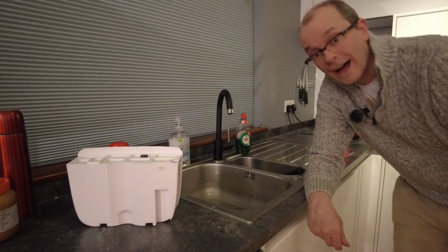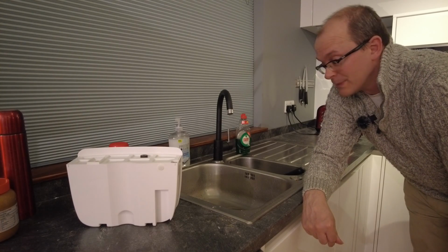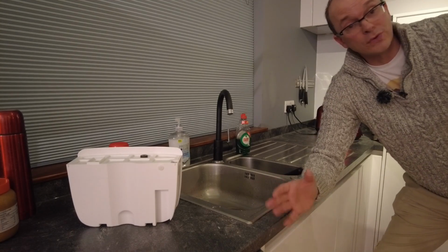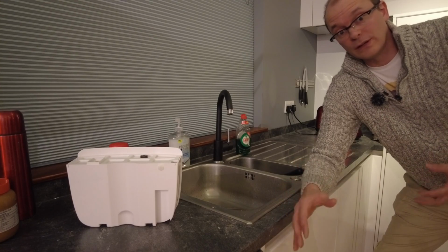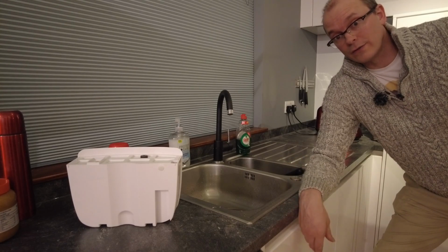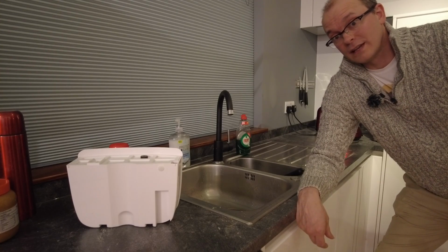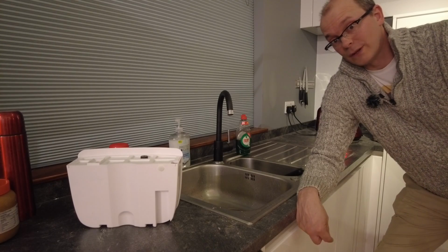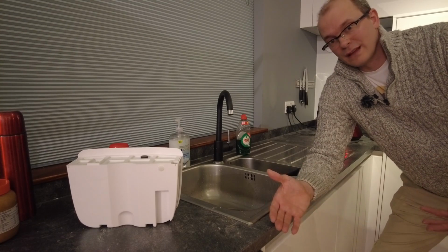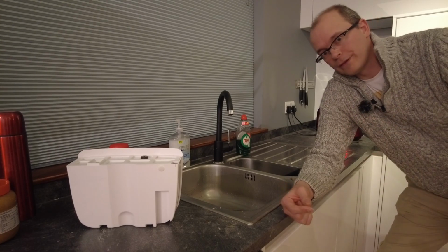Well, that is the amount of water that I accumulated over the last 8 hours of operation. And this is water which is being pulled out of my kitchen and the building fabric. It's worth bearing in mind that it's not just pulling moisture out of the atmosphere. There's moisture built into all of the fabric of your building, including the plasterboard and also any carpets that you may have. So that's a very useful amount of latent heat released back into the atmosphere. So it makes that cheap overnight electricity consumption even more efficient than before.